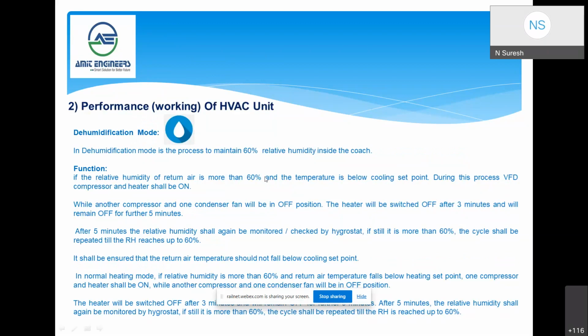There is a hygrostat also provided in the return air. Each unit has one hygrostat. So in case the relative humidity goes above 60%, the system will work accordingly.